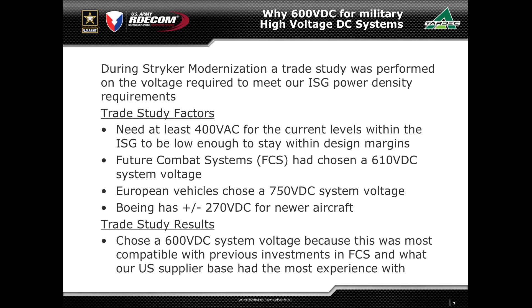At the end of the day, we just went with 600 volts, mostly because it was most compatible with the previous FCS investment that had happened, and we wanted to give U.S. suppliers, which had worked with that, the largest chance of competing, because at the time they had not dealt with the 750 volt that was solely European. So that's really why we chose 600 volts. Now, the reason we couldn't do 610 is because the actual voltage specification for FCS was proprietary to one of the vendors, so we had to do something slightly different to have our own voltage standard.